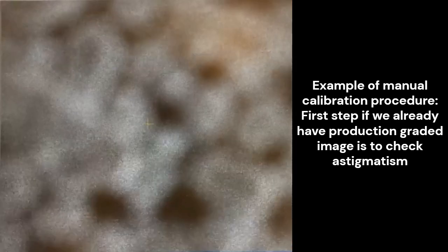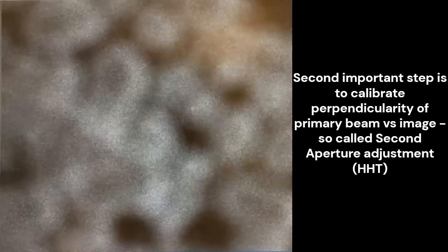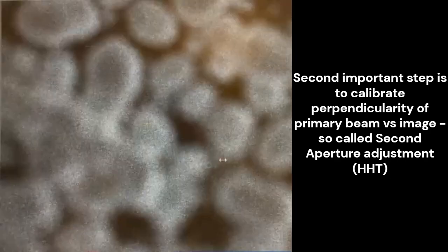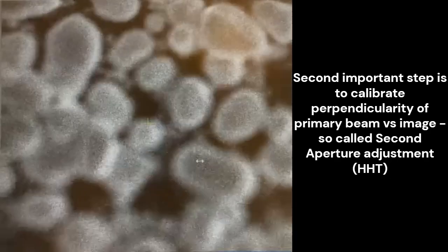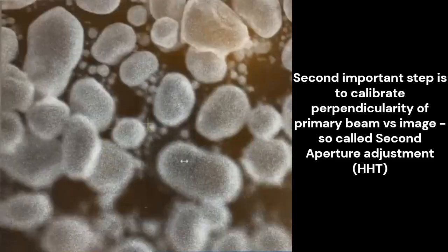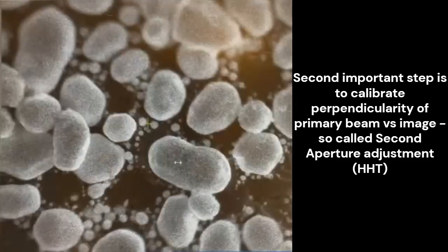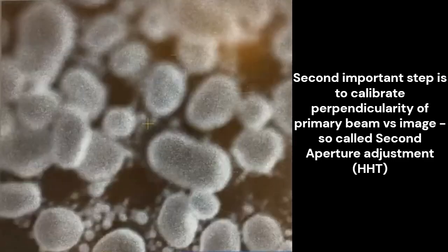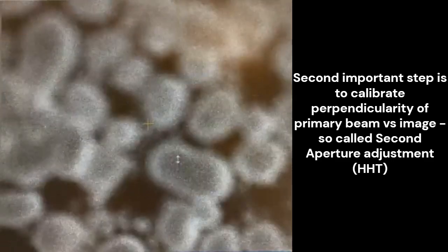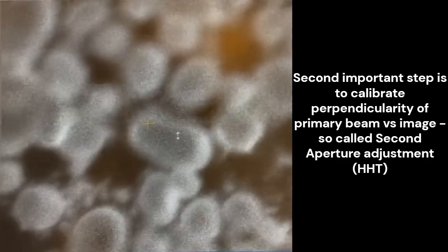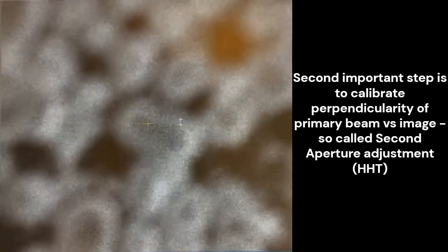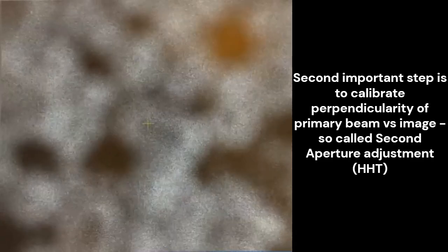And here again, it's moving along this diagonal, and I'm going to fix the lens alignment one axis at a time. If I want to fix the X oscillation, I'm going to grab the vertical bar of the lens alignment cursor, and move it left or right. As I move it to the left, now it's pretty much only moving up and down, so I've gotten rid of the X oscillation. To get rid of the Y oscillation, I'll grab the horizontal bar and move that up or down. Somewhere around here, it's basically blinking in place, and that's what we want to see.